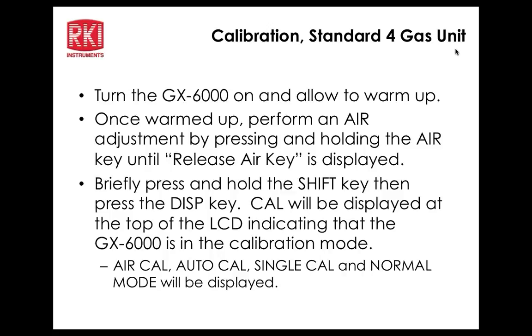Okay. Any other questions or comments on calibration? Okay. We'll go ahead and continue then. Oh, Daryl asked a question. I'm sorry, Daryl, you asked a question about the oxygen calibration. Yes. You may be able to set it less than 18% or higher than 18%, but there's a good chance you're going to fail the calibration. We don't recommend anything lower than 10% or higher than 18% for the oxygen. Okay, what was the low range? 10.